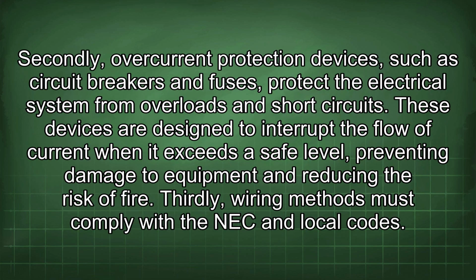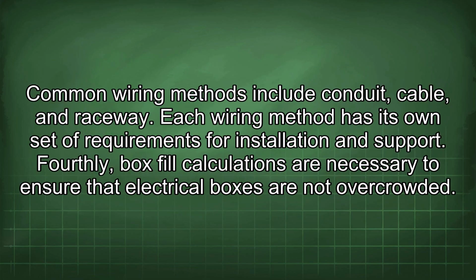Secondly, overcurrent protection devices, such as circuit breakers and fuses, protect the electrical system from overloads and short circuits. These devices are designed to interrupt the flow of current when it exceeds a safe level, preventing damage to equipment and reducing the risk of fire. Thirdly, wiring methods must comply with the NEC and local codes. Common wiring methods include conduit, cable, and raceway. Each wiring method has its own set of requirements for installation and support.